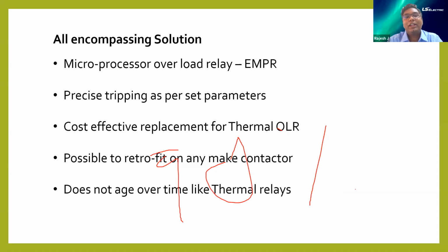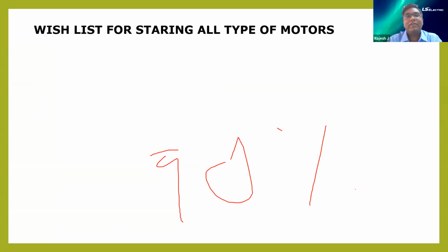It does not age over time like a thermal relay. Since it's microprocessor based, there is no mechanical or thermal life limit like a bimetal strip, so we are superseding that too. It is suitable for trip classes, as I mentioned for the trip curve, 10A, 10, 20, 30. So it's a single device which will take care of all the tripping classes. This is my last slide, then Mr. Dhaval will take it forward. So what is the wish list?